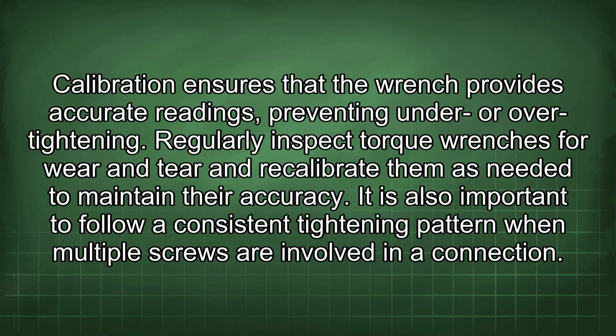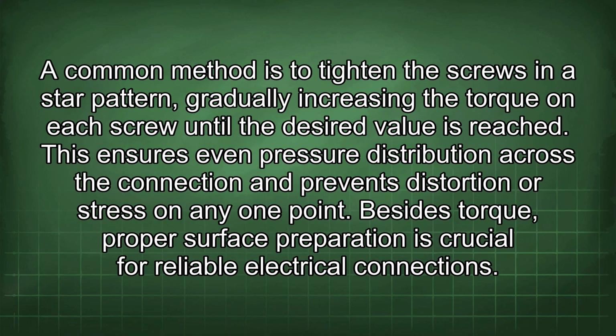It is also important to follow a consistent tightening pattern when multiple screws are involved in a connection. A common method is to tighten the screws in a star pattern, gradually increasing the torque on each screw until the desired value is reached. This ensures even pressure distribution across the connection and prevents distortion or stress on any one point.